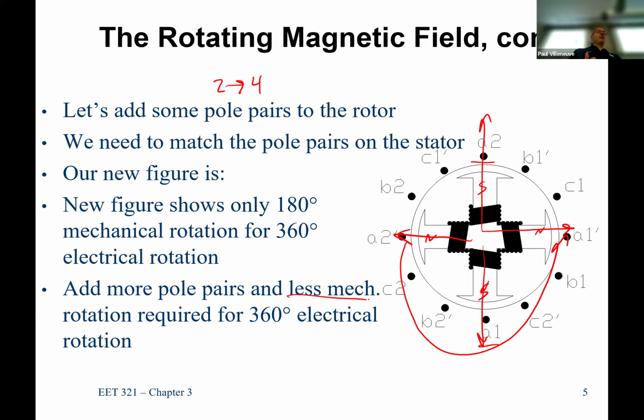That's the way to get a motor that operates at different speeds: I double the number of poles, going from 2 to 4, and I get a different speed. Most motors are 4-pole machines, mainly because of the mechanical systems. It's easy to make mechanical systems that run around 1800 RPM, but more difficult to make ones that run at 3600 RPM.